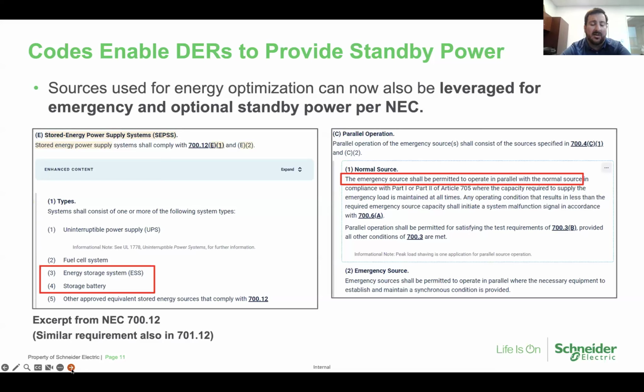And this excerpt from Article 700, which is around critical facilities, and you'll see similar phrasing in Articles 701 and 702 and others. You can see that it's explicitly mentioning that energy storage systems, implying battery energy storage systems, are allowed now as sources for standby power. Beyond that, the code also goes on to mention that the emergency sources, in this case the battery storage system, can be used to operate in parallel with other sources. You see that on the right-hand side over here, specifically the normal source. Next slide.